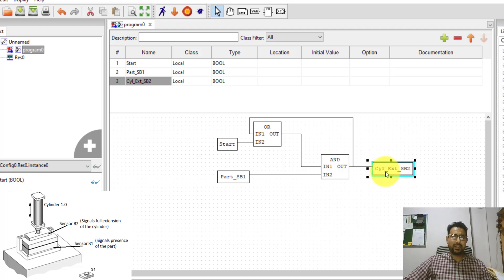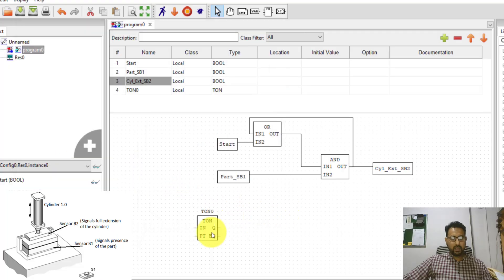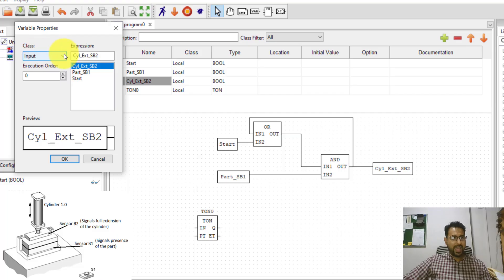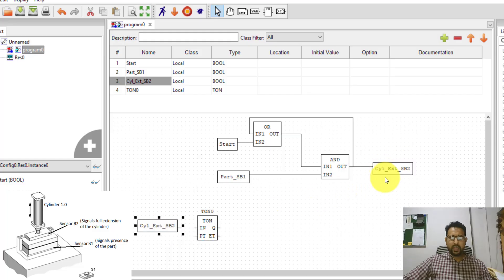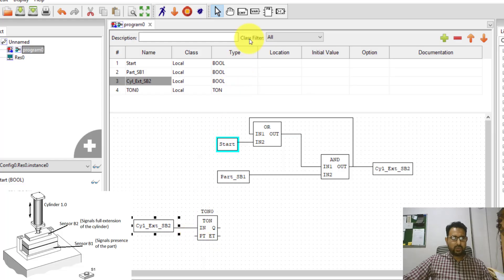I want a timer for 5 seconds. I can insert a timer by clicking on the function block and selecting a TON timer from the standard function blocks. I want this timer to run when the cylinder extend variable is on, so I insert that variable again as an input class. This output variable and this input variable share the same value. I connect it to the TON timer. To assign a preset value, I need to define a constant expression.